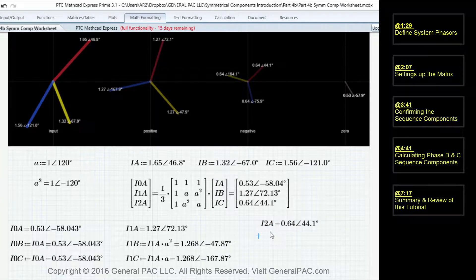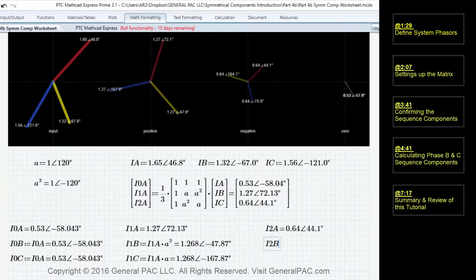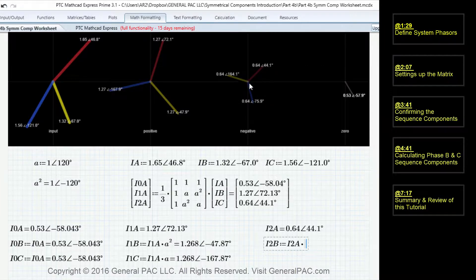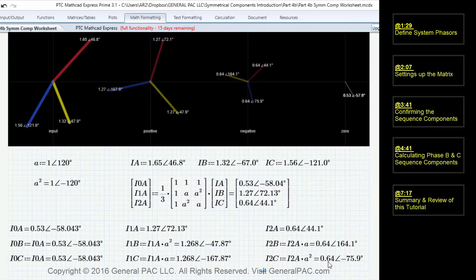For the negative sequence component, phase A is 0.64 at 44.1 degrees. To calculate the negative sequence for phase B, we take phase A and multiply it by the A operator, rotating it 120 degrees, giving us 0.64 at 164.1 degrees — which matches up. For phase C, we take phase A and rotate it 240 degrees, giving us 0.64 at negative 75.9 degrees.